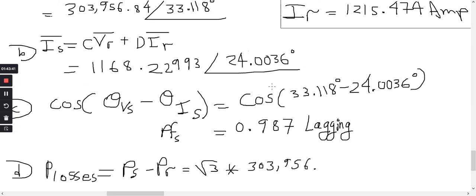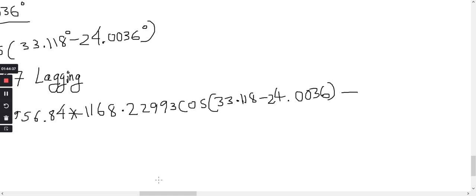So it's square root 3 times V times I, that's the V sending and that's the I sending, times the power factor cosine of the angle, which is 33.118 minus 24.0036, minus the P at the receiving end, which is already given as 1000.